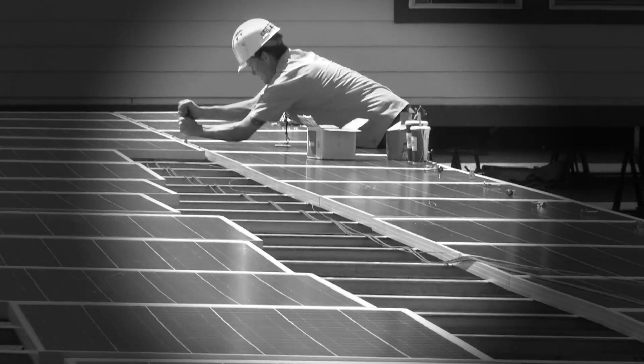In many cases, there are 30,000 panels, and they all have wiring that comes out of them. It's around a lot of sharp edges of metal, and it's very easy for one of those wires to get skinned. The grid has to be a complete grid, they're not insulated from each other, a continual grid of continuity, so if there is a fault, it goes to ground. If it's an ungrounded system, whatever comes in contact with it that is grounded will become the path of least resistance for the electricity to flow to ground. And that'll go right through your heart, and that's where you either get burnt or you die.